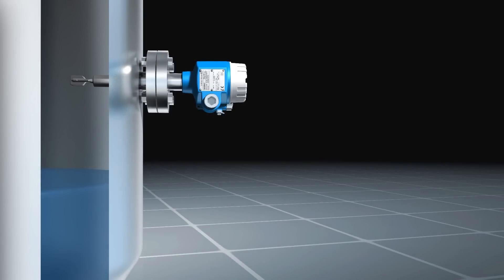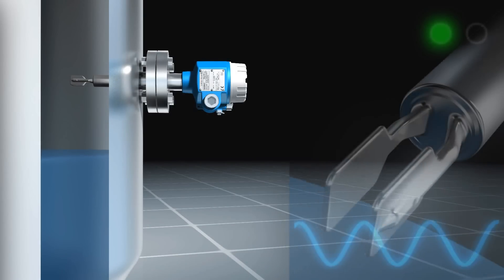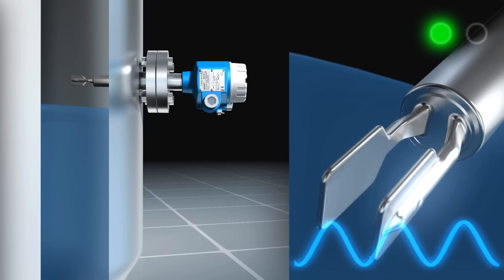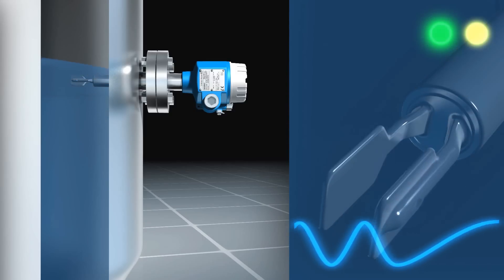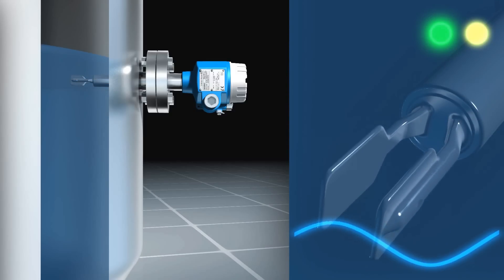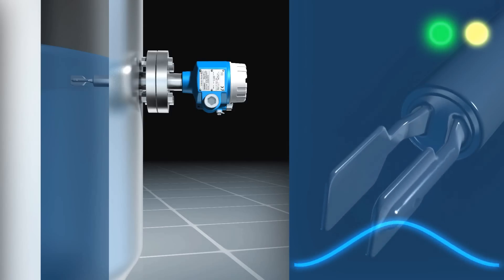As the tines of the fork are covered in a tank as the liquid rises, the resonance frequency of the tuning fork changes. The immersion into the liquid reduces the frequency. This frequency change is analyzed and converted into a switching signal.